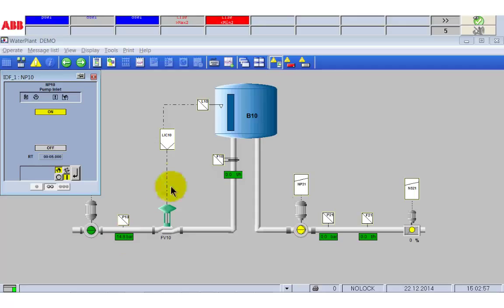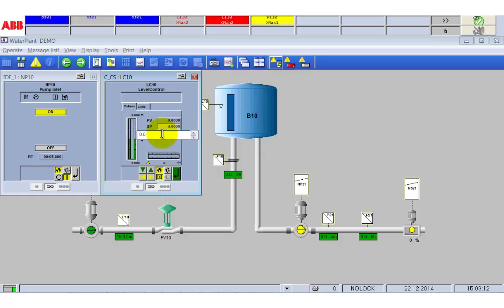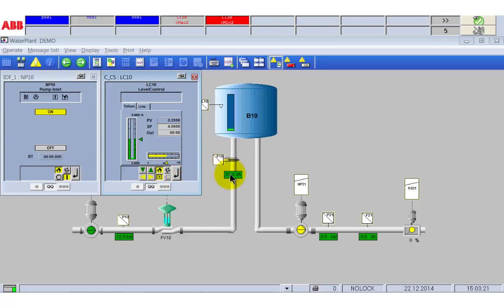Let's now open the valve. Click the LIC10 label which opens the corresponding face plate. You see that the set point SP and the out value are adjustable in manual mode. Therefore you may force the out value which controls the positioner to 60%. The flow reaches a value of 32 tons per hour and the water level in the tank is rising.